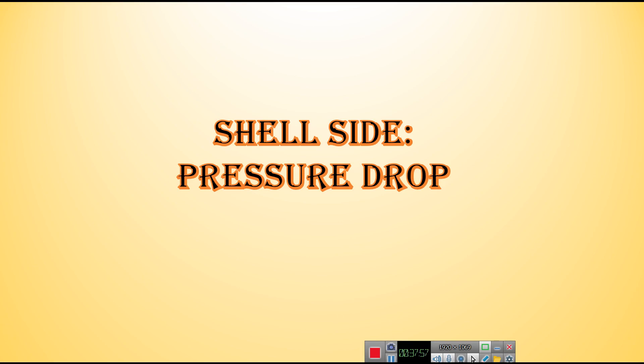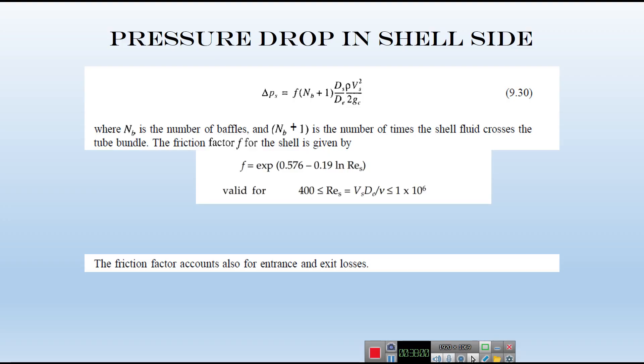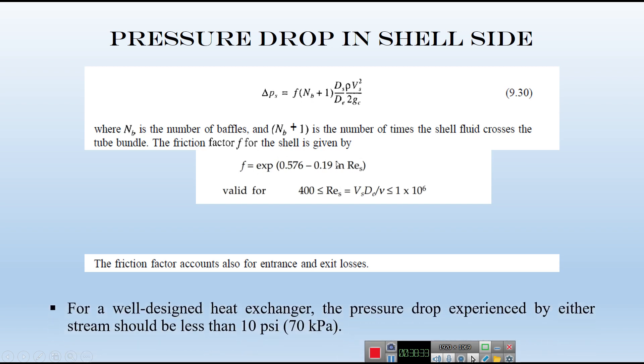For shell side pressure drop, use the correlation: ΔP depends on N_B (number of baffles), D_S, D_e, V_S, and a friction factor F found from a specific shell-side correlation — do not use the Moody's diagram for the shell side. G_C is 1 for SI and 32.2 for British units. Ensure shell side ΔP < 10 psi or 70 kPa.